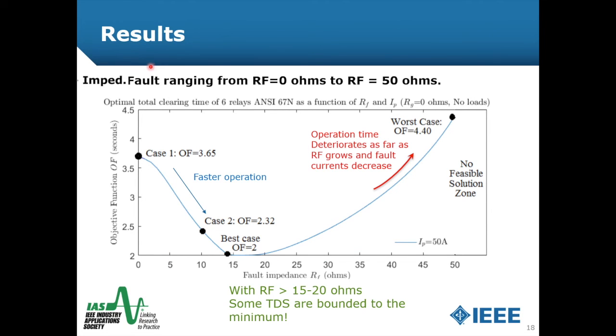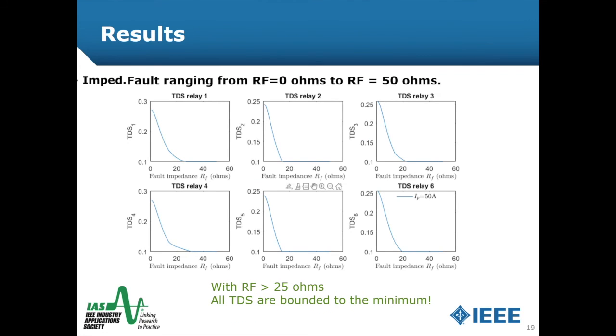We checked the general performance of the objective function from zero impedance up to 50 ohms. Starting from case one, the objective function decreases, reaching faster operation until it breaks in the range of 20 to 50 ohms. After that, the operation time deteriorates as fault resistance grows, meaning some TDS values are bounded to their minimum. This is also shown for the performance of each of the TDS values of the six relays across the 0 to 50 ohm range.